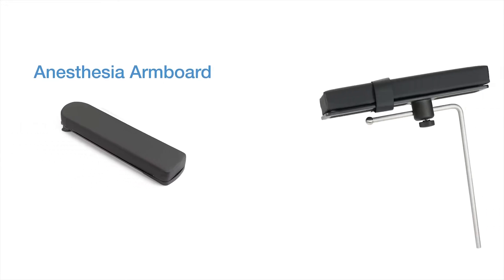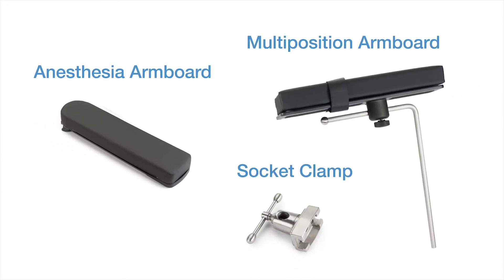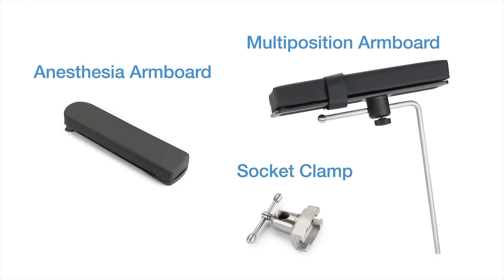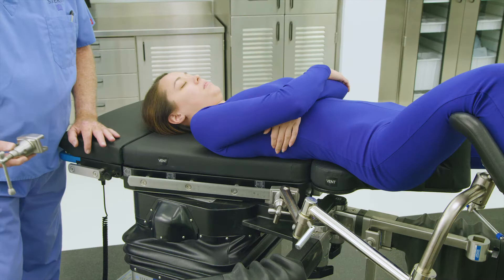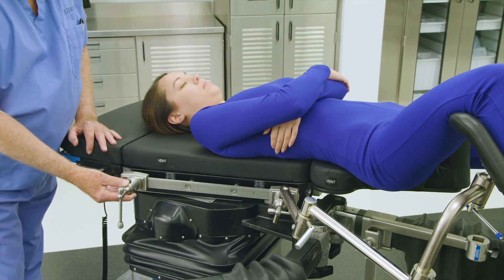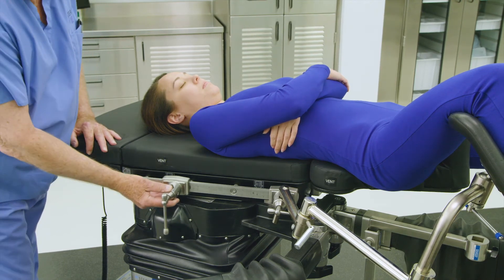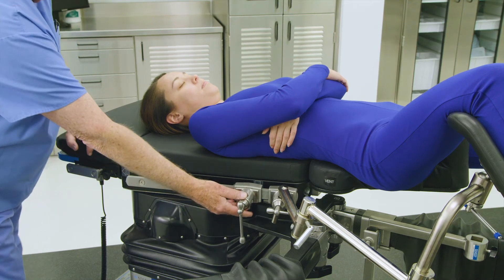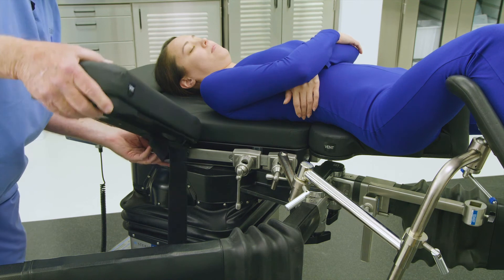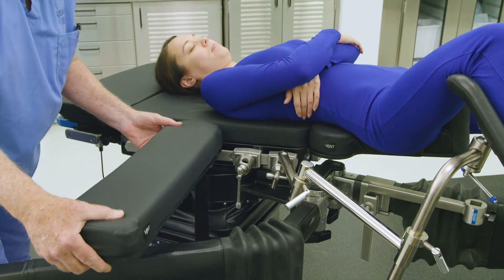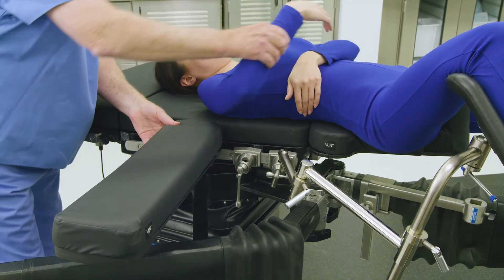The OT-1000 series table is equipped with both an anesthesia arm board to help position the arm on the non-operative side of the body, and a multi-position arm board to help position the arm on the operative side of the body, to ensure patient arms are properly positioned during the procedure. Before attaching an anesthesia arm board, first apply a socket clamp to the side rail on the non-operative side of the table. Next, apply the standard anesthesia arm board to the side rail on the non-operative side and adjust as needed to accommodate proper arm position.